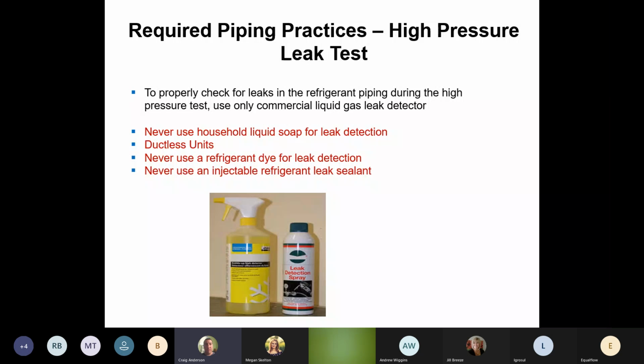On standard AC units, they're allowing leak dye to go into the system and refrigerant leak seal. We've been told by Yellow Jacket that the tools they've seen come back, like vacuum pumps, gauges, stuff like that, are really not being affected by this stuff. The only time we don't want the dye and the refrigerant seal leaking is when we start dealing with ductless splits, because of the strainers and the small diameter of piping we're dealing with. We don't want any of that stuff in a ductless split system.